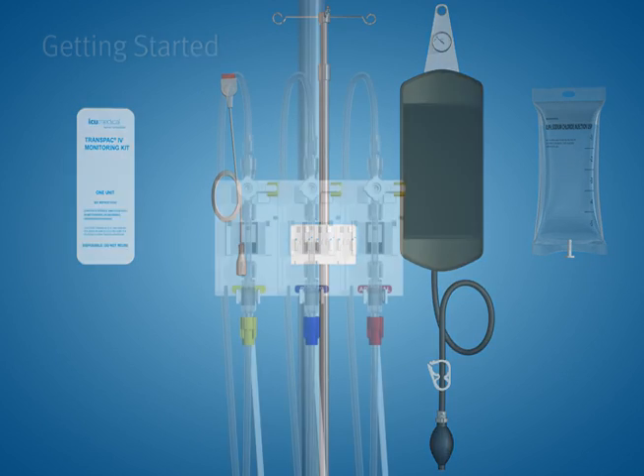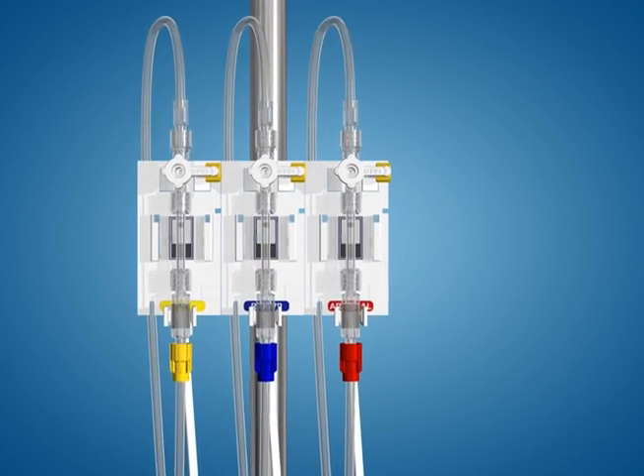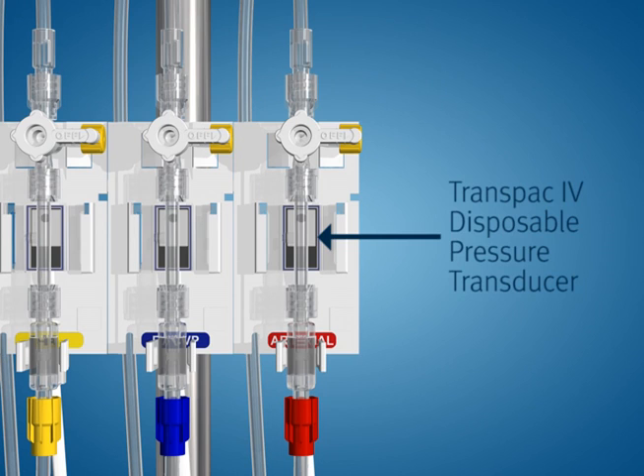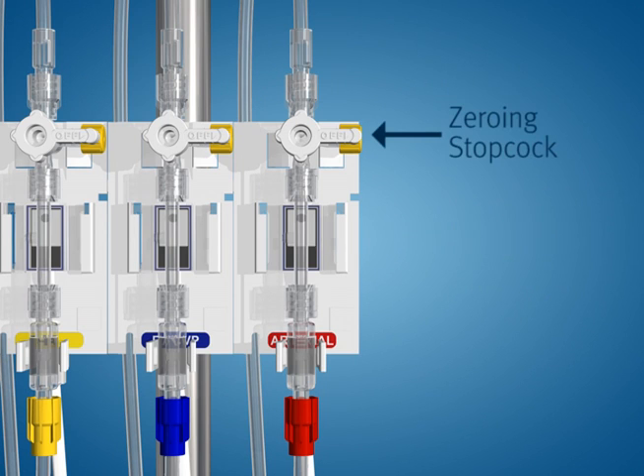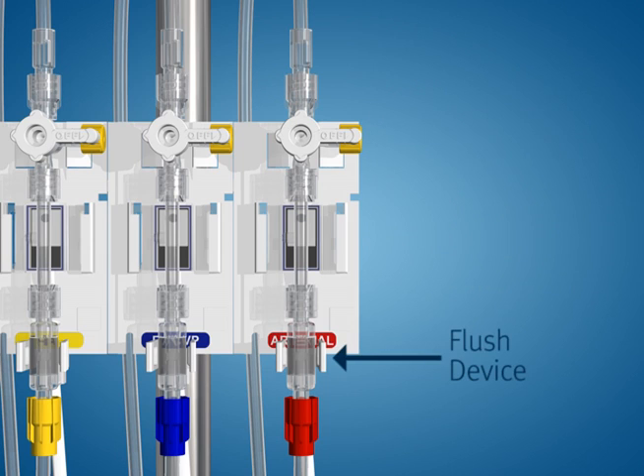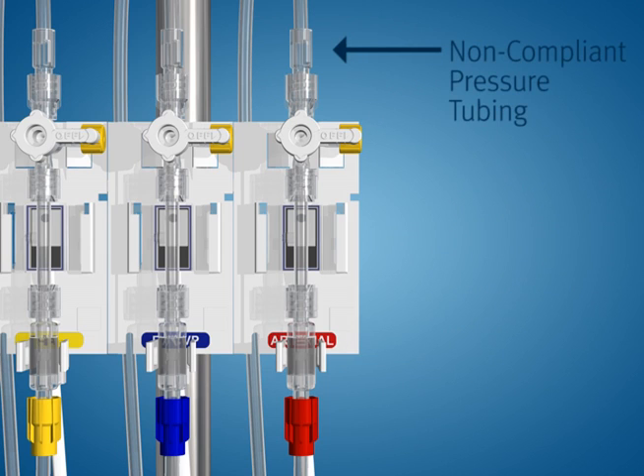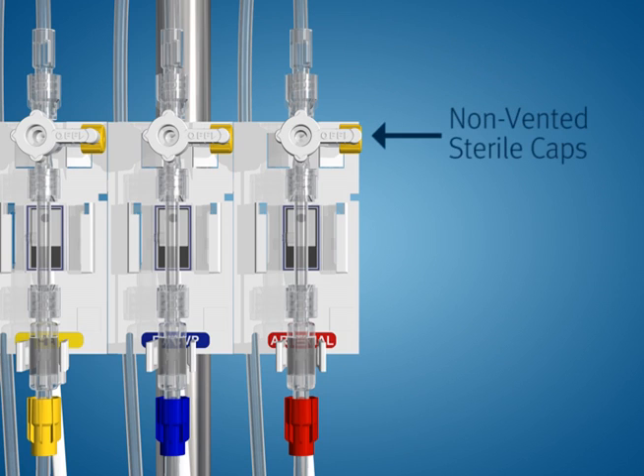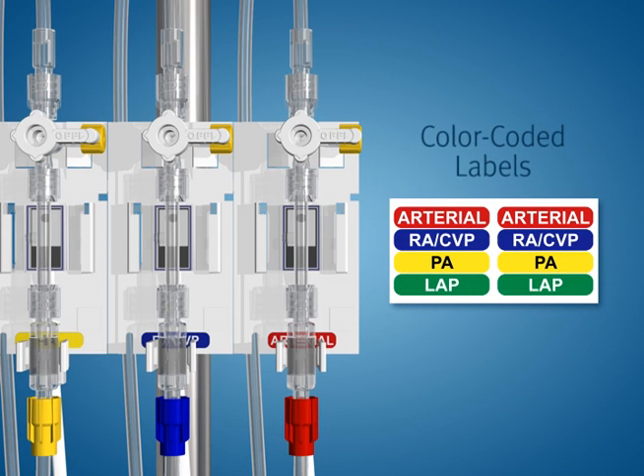kit. The key components of a Transpac 4 transducer kit are the Transpac 4 disposable pressure transducer, the zeroing stopcock, the flush device, non-compliant pressure tubing which helps to ensure accuracy, non-vented caps to maintain the sterility of the fluid path, and color-coded labels so you can identify the different lines when you are monitoring more than one pressure.